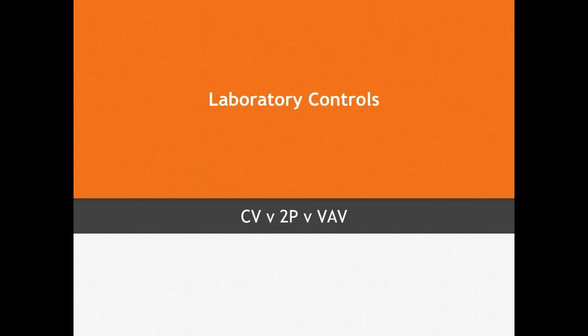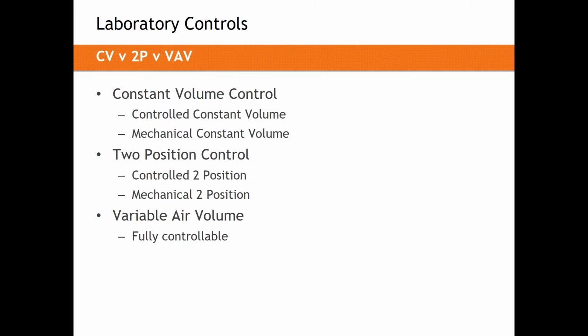So how can we start to apply what we know about valves now to laboratories and equipment? What we're going to break this down into is constant volume versus two position versus VAV. Now we'll start with high accuracy terminals and terminal units. All of them are VAV boxes. They are all variable air volume boxes. We sometimes see on schedules that a terminal unit can be called a CAV, or constant air volume, something like that. That's a bit of a misdirection.